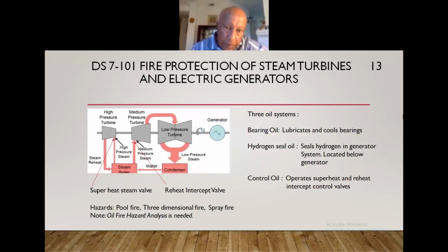And then hydrogen has to be detrained from the lube oil. So we have to put a spray system around the jet fire. We calculated that a 1/4-inch crack in the pipe can produce about 50 megawatts of energy, and that will heat the soft underbelly of the generator, and the generator insulation will melt. So we can reduce the temperature of that heat to about 500 degrees Fahrenheit to protect the generator.